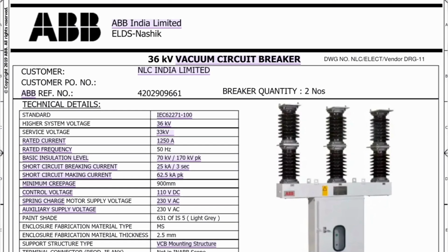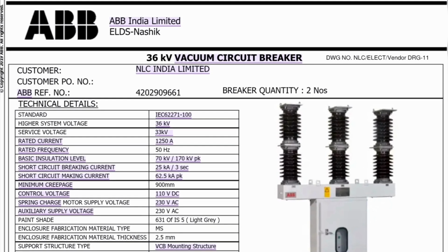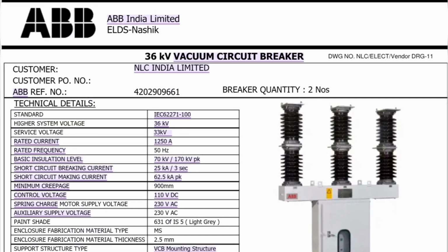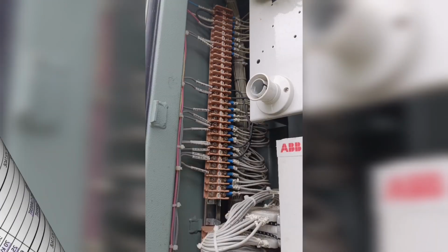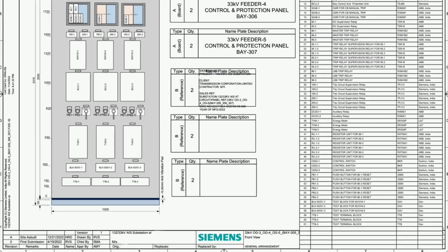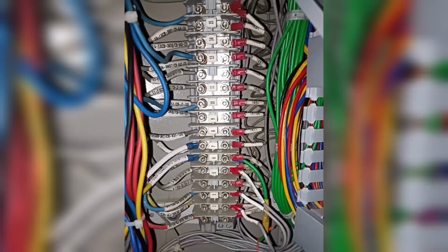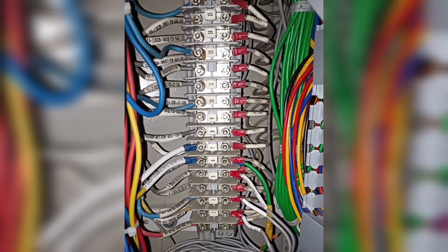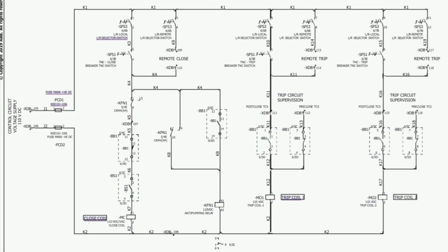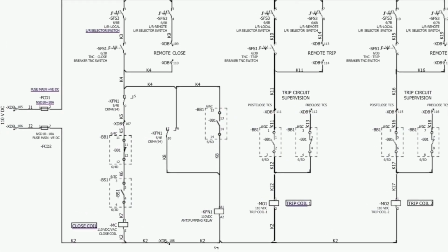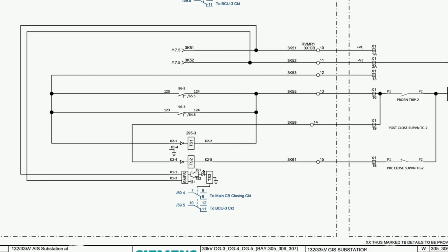Hello everyone, in today's video we're going to understand the complete control wiring and perform the step-by-step interconnection between an ABB 33 kilovolt vacuum circuit breaker and a Siemens Feeder Protection Panel. Whether you're commissioning a new substation, carrying out maintenance, or troubleshooting a circuit breaker control circuit, this video will help you understand the complete wiring logic from start to finish.